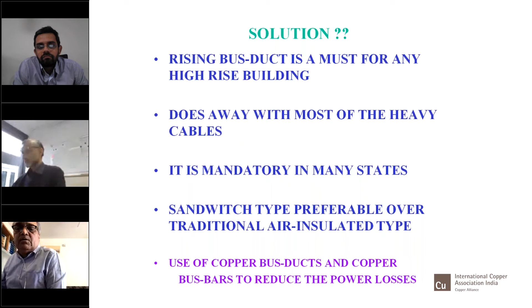Sandwich bus duct installation, this is an example. You can see a graphic showing how these bus ducts are arranged, with 1, 2, and 3 risers. On the ground floor there is an electrical room with transformers and other equipment, and these risers come up, with all the loads at every floor tapped from them. Other than this, there are no other cables running up and down except, of course, the communications and data cables, which don't produce fire or heat.